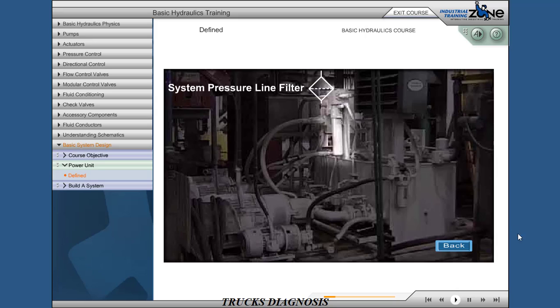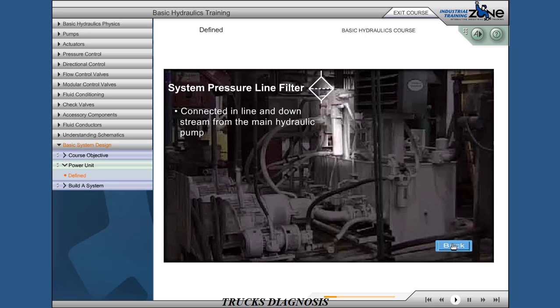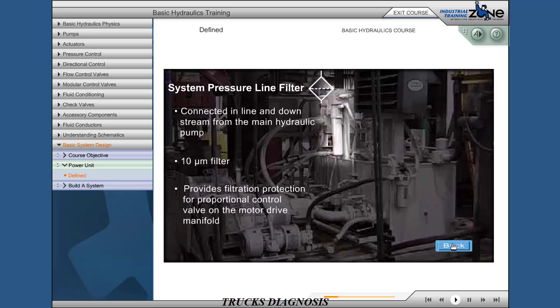System pressure line filter, connected in line and downstream from the main hydraulic pumps. 10 micron filter. Provides filtration protection for a proportional valve on the motor drive manifold.